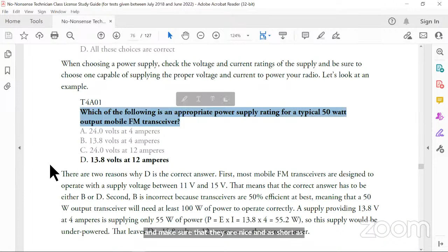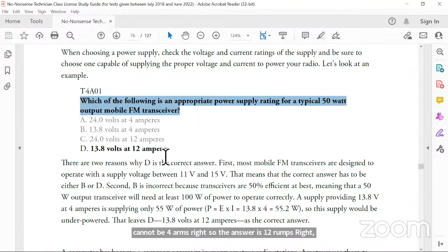Next question: which of the following is an appropriate power supply rating for a typical 50 watt output mobile FM transceiver? So you'll see why we did a little working there. First of all, it has to be 13.8 volts. The answer must contain 13.8 volts, not 24 volts or anything else. But then the two options that we have are 4 amperes and 12 amperes. When we actually did the calculation, remember we came up with 3.62, but we also said that the radio is not going to be 100% efficient, and we should not have a power supply that is exactly rated for what we need to use. We need to have some headroom. So it cannot be 4 amps. So the answer is 12 amps. So for that 50 watt transceiver, 13.8 volts at 12 amps. That's the power supply rating minimum. Okay, next question.